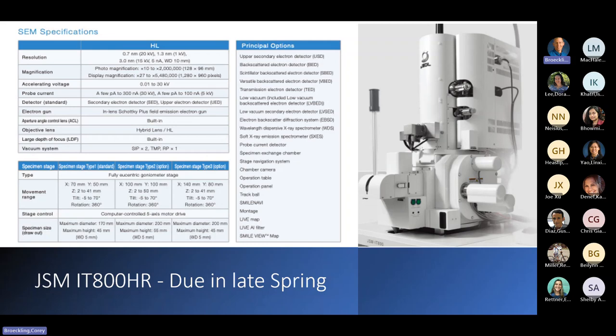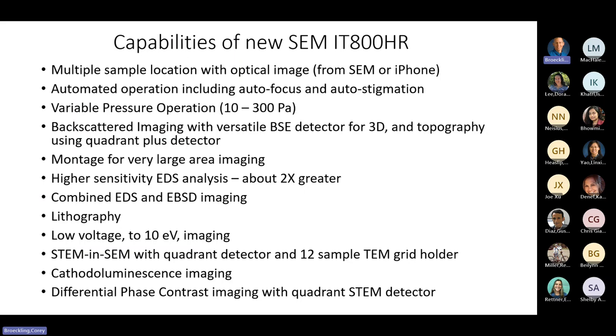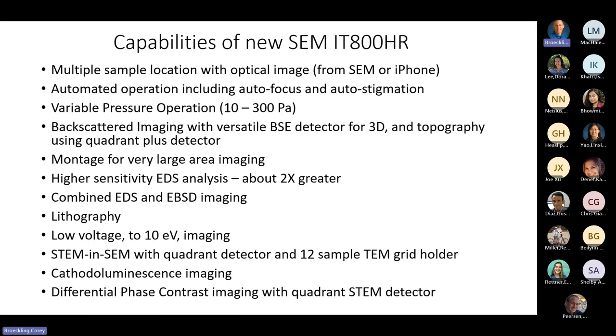The big thing that this one pushes is variable pressure and the low voltage. You can take your optical picture with the SEM or your iPhone. The automated operation, I'll show you examples of this. This is really useful for casual users where you can autofocus or auto-stigmate the image. It has variable pressure, you can do the backscattered, the montage, high sensitivity EDS. This will have the 170 millimeter squared EDS detector. So it will be at least twice as sensitive as what we have now.